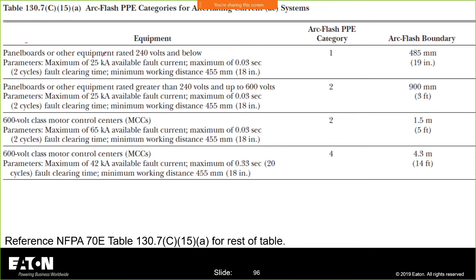So the way apprentices and journeymen are trained when they're looking at 70E, they know that as long as I can identify a molded case circuit breaker, if I'm on a panel board 240 volts and below, I'm in PPE category 1. If I'm in a panel board that's between 240 and 600 volts and I'm downstream of a molded case circuit breaker, I'm in PPE category 2. So depending upon where I'm at, and as long as I don't have more than 25,000 amps, I know exactly how I can dress very quickly.